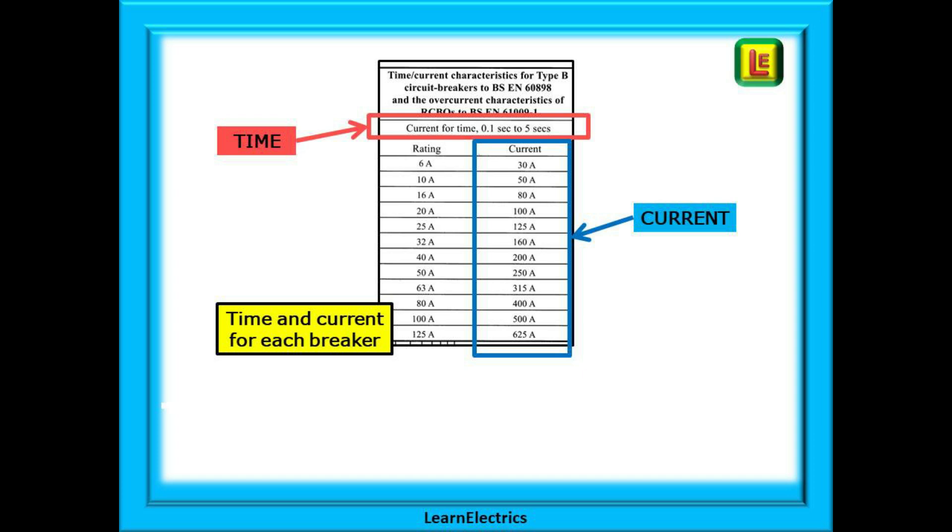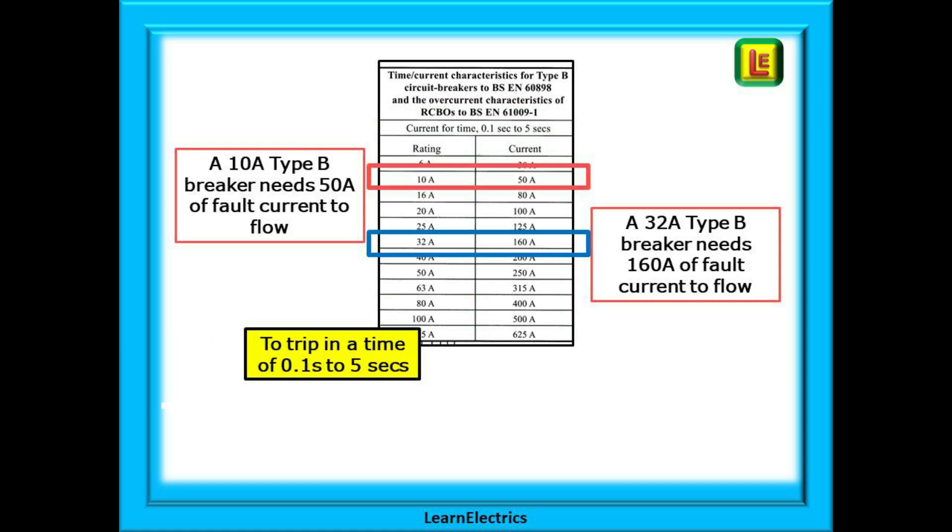Look closely at the box. It indicates the time at the top, the red box here, and the current is in the blue box. It tells us the time and current for each size of breaker or RCBO. A 10 amp breaker needs 50 amps of fault current to operate in the time indicated whilst a 32 amp device requires a lot more, 160 amps.